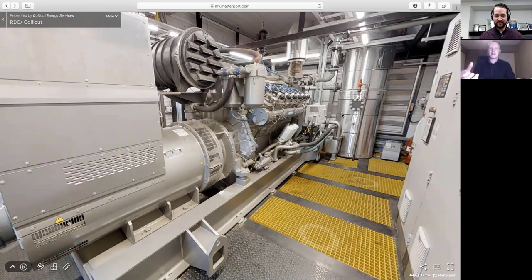It's taking heat from the exhaust, bringing it from about 450 degrees Celsius down to 120 degrees Celsius, so there's a pretty big temperature change on the exhaust side. Meanwhile we're taking the water temperature from about 60 degrees to 80 degrees. It really shows you how much more energy there is in water temperature rise than there is in the exhaust.